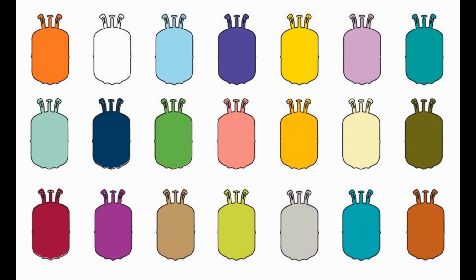Refrigerants work by using a process called the refrigeration cycle to transfer heat from one location to another. The basic components of a refrigeration system include a compressor, condenser, evaporator, and an expansion valve. 1. The compressor compresses the refrigerant gas, which raises its temperature and pressure. 2. The high-pressure, high-temperature refrigerant gas then flows into the condenser, where it releases its heat to the surrounding air or water and condenses into a high-pressure liquid.